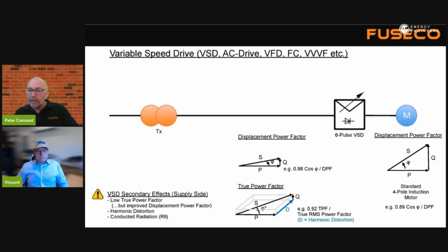So apparent power on your bill would be shown as kVA, or kVA hour, but it's a makeup of kVAR, the reactive component, and kilowatt combined. So we're going to come back to that, and maybe how to reduce this triangle down to the same length as P. That's when you can save on the reactive power, and save on your kVA hour costs.